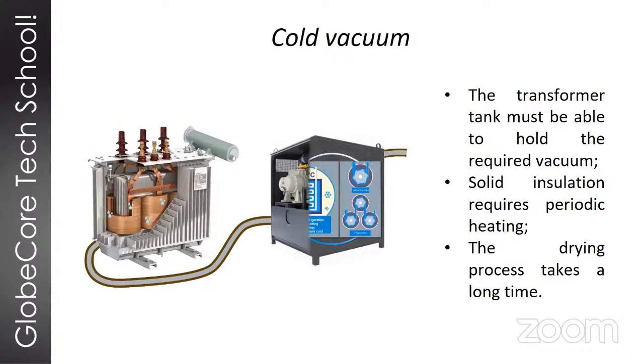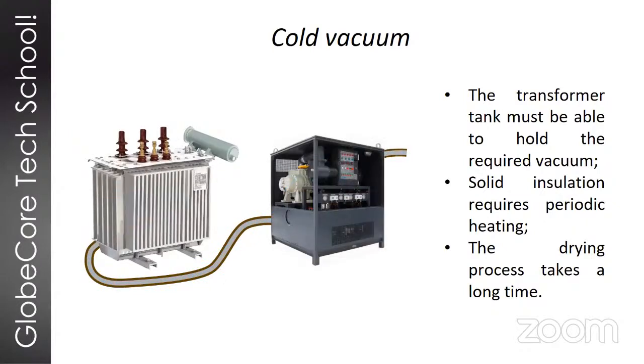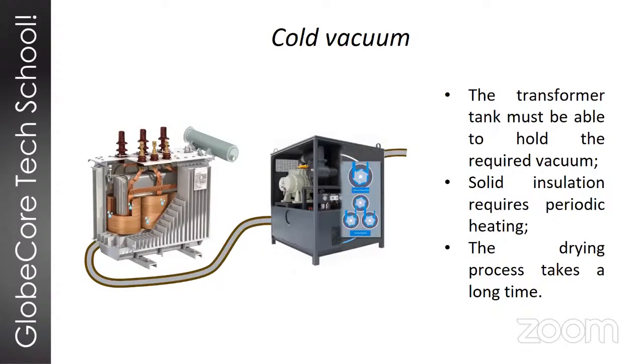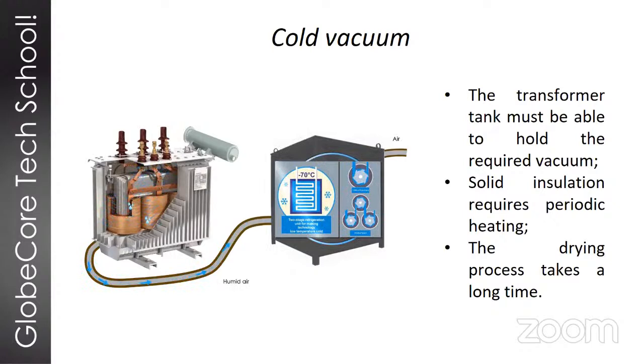The cold vacuum method can be used usually for small and medium-sized transformers, and can be used on site. The limitations here, again, because we use vacuum, the transformer tank must be strong enough, and also the process is long. So to efficiently remove water using a cold trap, we also need to heat the insulation periodically, and these cycles take quite a bit. And to dry a transformer in this manner, you might actually need several weeks. Okay. Next slide, please.